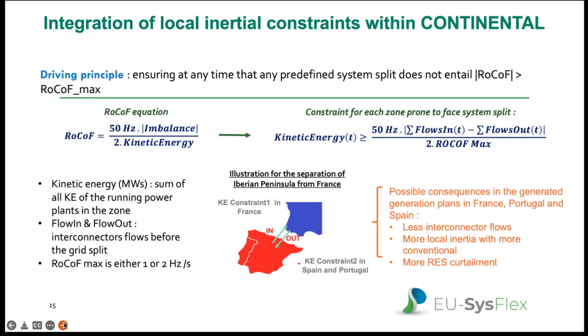So enough kinetic energy so that in case of grid separation from the rest of Europe, the big imbalance caused by the interruption of interconnect flows would not entail very high rate of change of frequency. For instance, max ROCOF could be set to 1 or 2 Hertz per second. If we apply this constraint, for instance, in the case of the Iberian Peninsula as we did, that means at any time Continental has to decrease a little bit the interconnect flows, or maybe has to put more conventional units in order to increase the level of inertia. By these two actions, we're going to secure the system in case of grid separations. But obviously these two actions will have some consequences in terms of cost, so financial consequences.